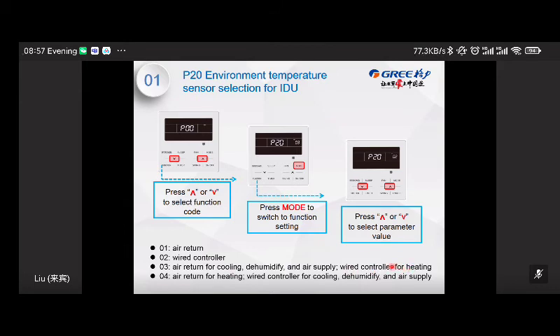That's the default one. However, you can change it so that no matter cooling or heating, the units use the air return for the ambient temperature detecting, or just the wire controller, or the opposite: the air return for heating and wire controller for cooling. For heating and cooling, because of the density of the hot air, right, the detection of the ambience may be not precise. You can change the location of that sensor to detect more precisely and to make the air conditioning more comfortable.